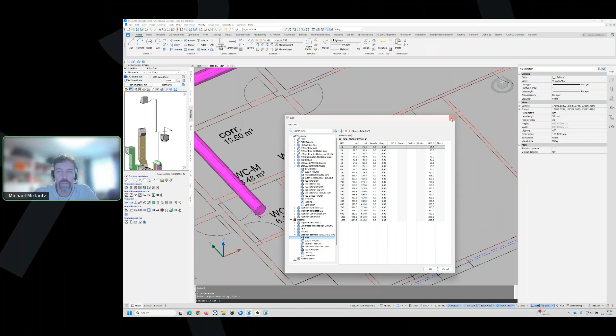There's a pipe database in the background, one database used for all the different disciplines. I have a ventilation discipline, and there are pipe cross sections available. If I don't like one, I can copy, move, or add one. Same goes for heating or sanitary. It's also important to know the internal and outside diameter, because the internal diameter is used for velocity, Reynolds number calculations, and so on, while the outside cross section is used for leveling. For a plastic pipe you level the outside diameter, for a steel pipe you level the nominal diameter, and for a copper pipe you level the outside diameter and wall thickness, so the difference between outside and inside.